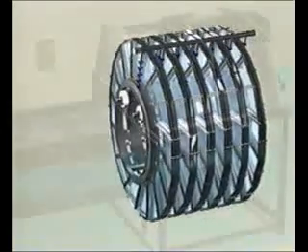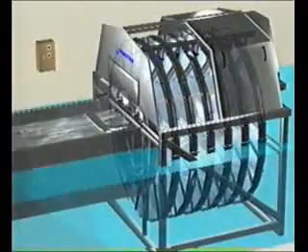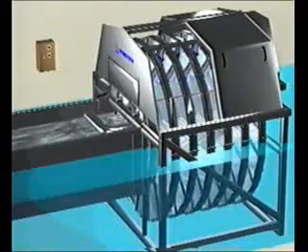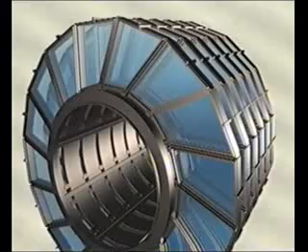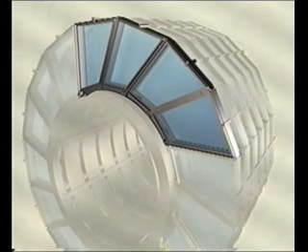A filter installation can be placed either in a concrete channel, in a basin, or as a freestanding pipe-fed filter equipped with a stainless steel tank. Each disc consists of a number of disc segments, 3, 4 and 5 respectively, depending on the size of the filter unit. Mounted on the sides of the filter segments are the filter panels. Each panel is equipped with a rubber gasket and held in place by means of a locking frame.